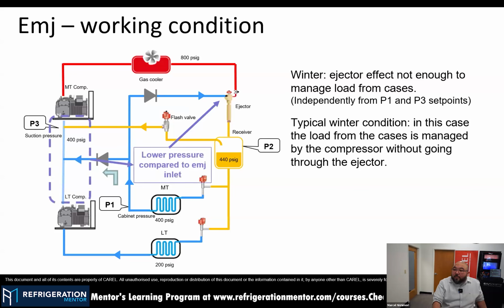And on the other side, during the winter, I have a mild condition on the gas cooler. So here I'm saying like 800 PSI as an example. It could be any pressure. Then I don't have that much energy to be wasted here on the high pressure valve during the expansion. So I cannot have a lower pressure zone here. So at this point, the suction here at the compressor side will have a lower pressure.